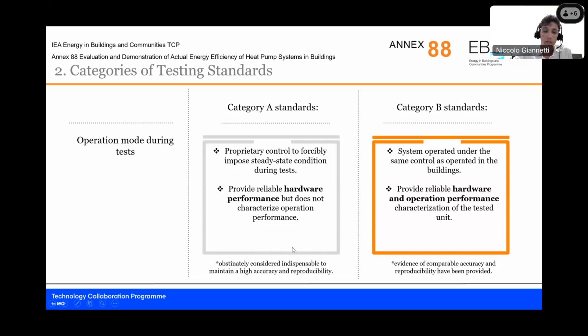So on one hand, many people consider that this kind of approach is somehow necessary to have high accuracy and a high reproducibility level of the results. However, with this report, we bring in some new opportunities for obtaining results that are as reliable, but representative not only of the hardware performance of the unit, but also of its operational performance. During this test for category B, the system is always operated under the same control as operated in buildings. So there is no need for any addition or connection to special proprietary control during this test.